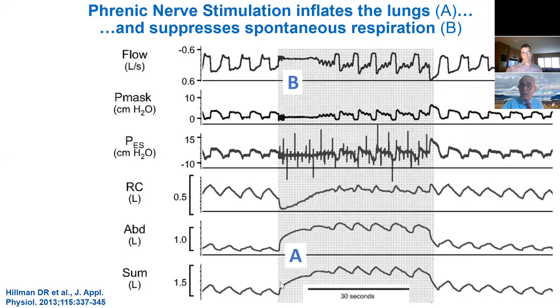And as the lungs inflate, what we see here is that respiratory effort and all airflow ceases. In other words, we've captured the diaphragm. After all, that's how the lungs inflate. But we've also, in the process, induced an instantaneous, spontaneous cessation of respiration. We have ceased or suppressed the patient's own spontaneous respiratory efforts for a period of at least 5 to 10 seconds. Well, that becomes the key, because if we do this and there's an instantaneous response to stimulating or capturing the phrenic nerve, then the rest is all downstream.